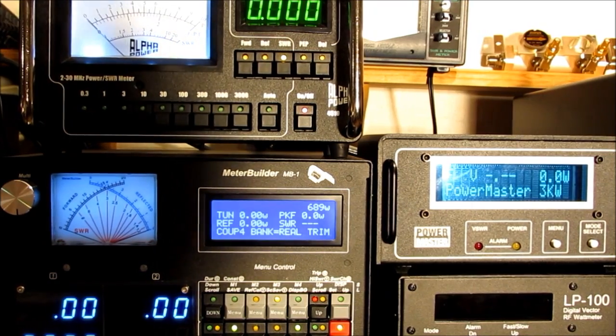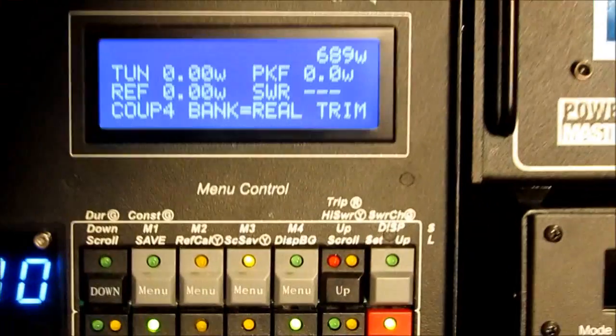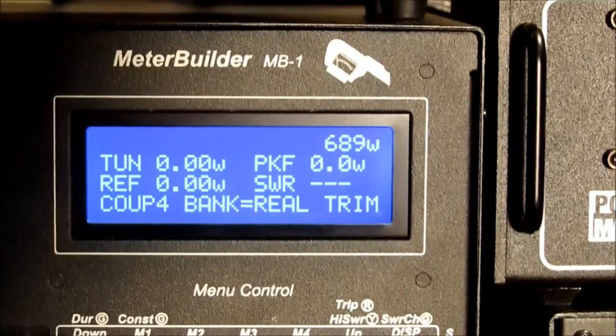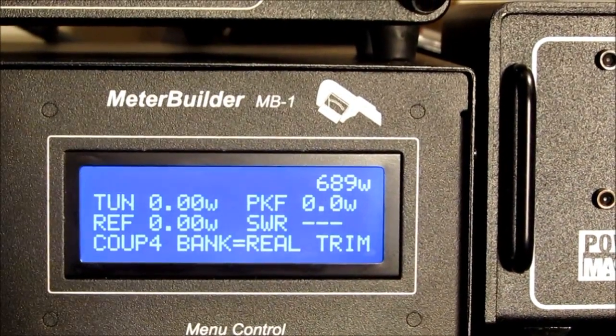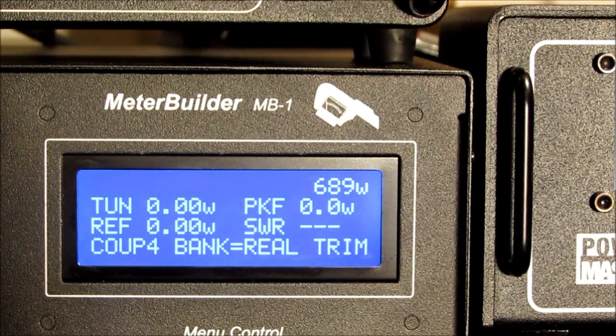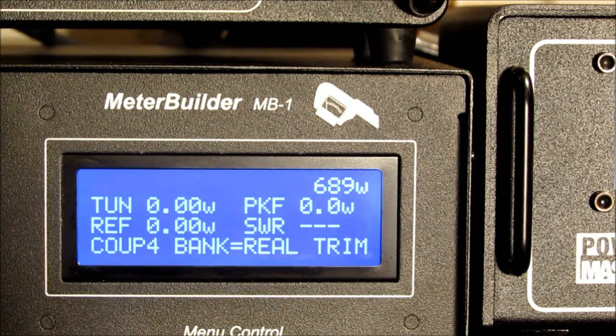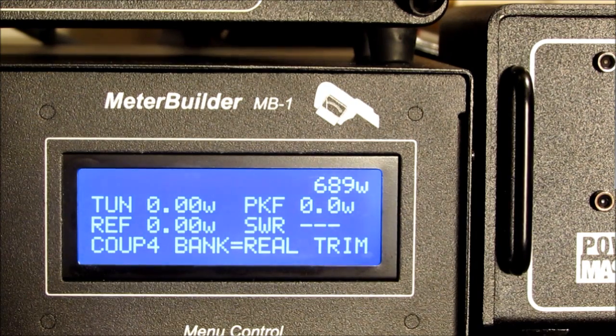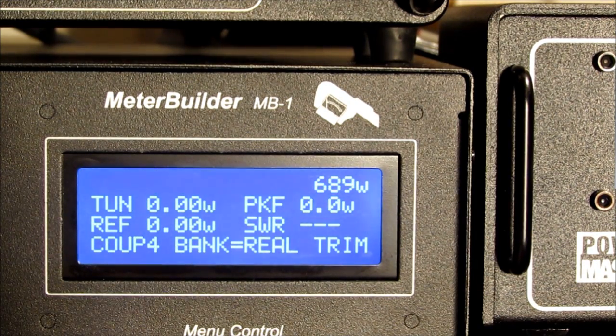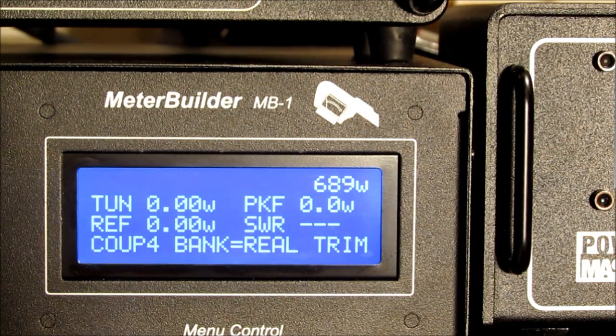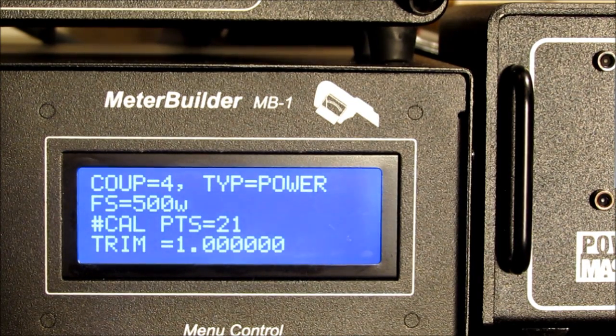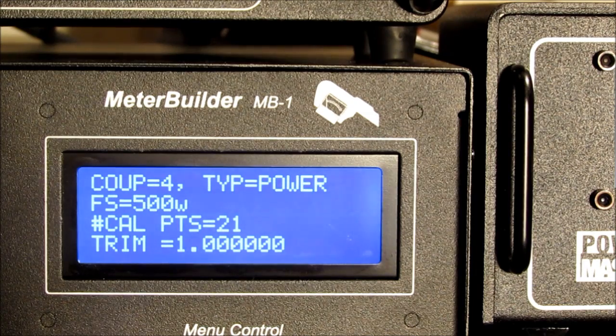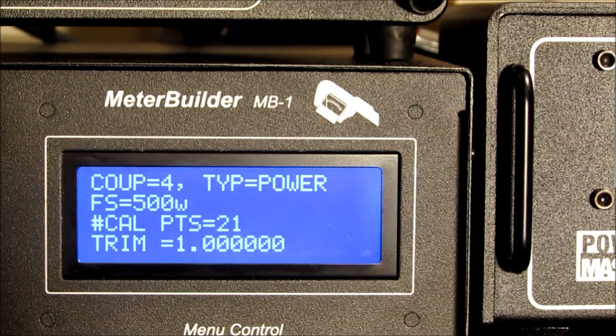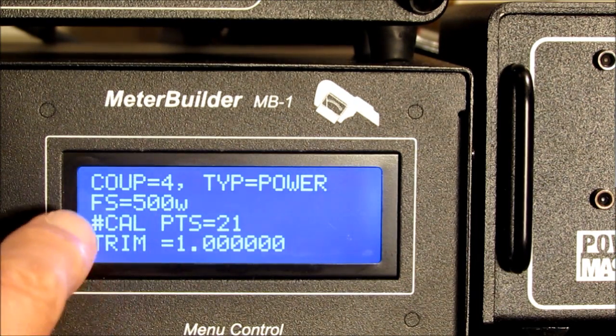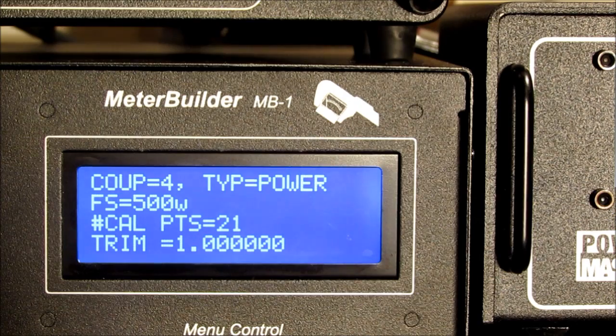Now I just want to show you, let me zoom in on the coupler. We mentioned that this is a dual purpose switch. It allowed us to go into the setup mode. It also provides information. So let's go ahead and see what information we've actually stored for the coupler we've just calibrated. Okay, it's telling us that we calibrated at 21 points. It's a power coupler versus an RF current sensor or a generic meter application. Full scale power is 500 watts.